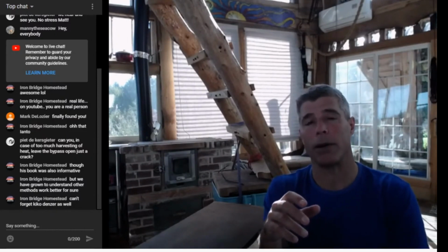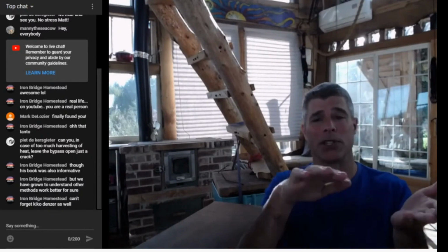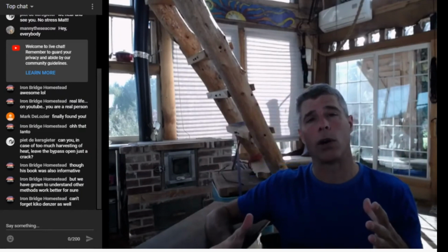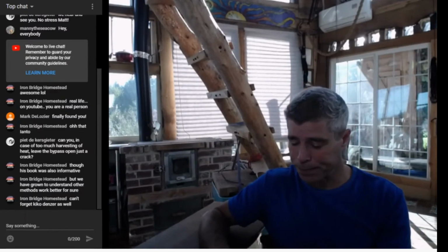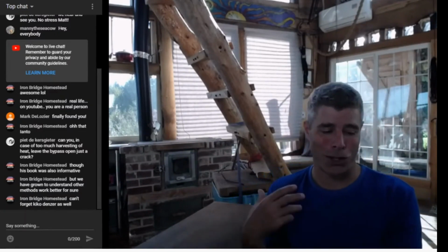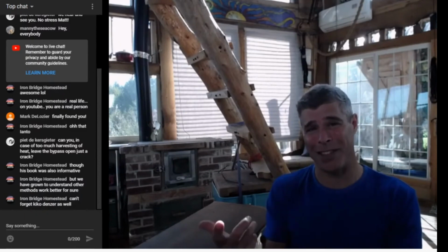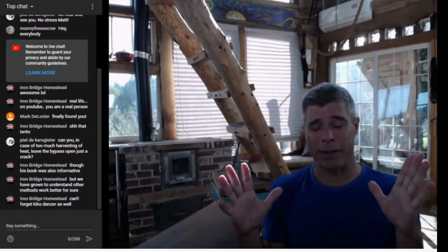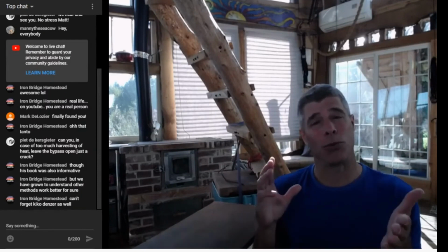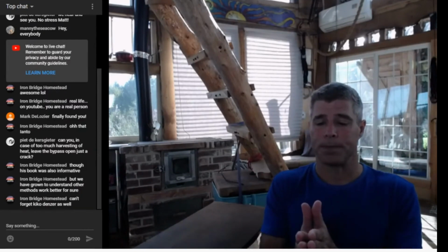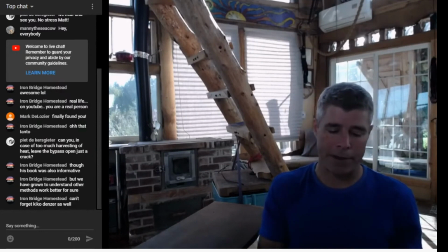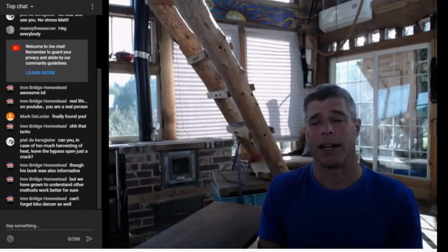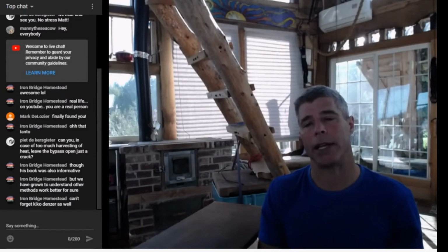And frankly, we talk about rocket mass heaters often. We talk about our builds, and we talk about bringing the gases below the core. So we do have descending gases, and they do go low quite often. So what I wanted to talk about in this chimney discussion was the difference between when the gases are in the masonry body of your stove, or when they're in a chimney, and how you should really consider those two parts of the stove to be completely separate modules. So don't look at the stove and go, well, we can have these descending gas paths, so it must be okay for the chimney to go downhill, because that's not the case.